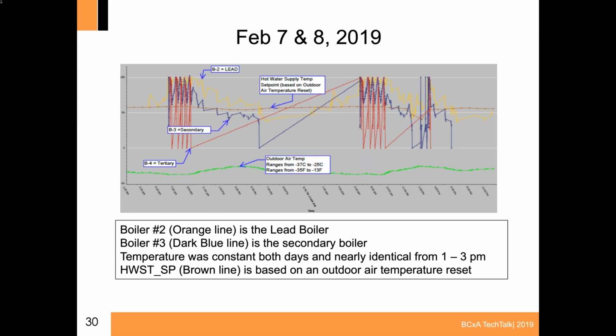So you can see that prior to our adjustment, 2 boilers were firing and sometimes 3. You can see the red line, which is the 3rd boiler that could come on, which cycles just massively as a result of programming in the sequencing that compares a temperature differential from a primary and secondary temperature system. So this is another issue that we found that's causing a lot of energy consumption.